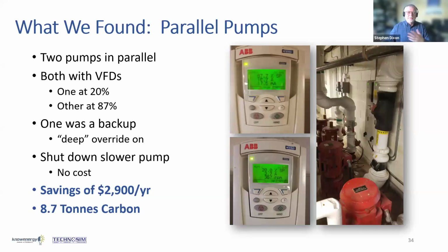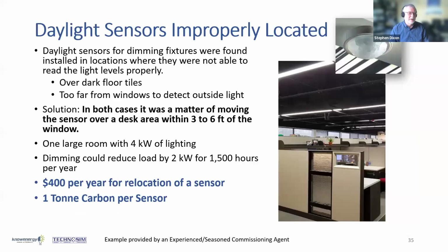As a result of some work, we did a treasure hunt in this building. I'll explain what a treasure hunt is later. It saved $3,000 a year and 9 tons of carbon just by turning off something that didn't need to be on, and equalizing the wear and tear in the pumps, because it turned out one pump was running all the time at higher flow than another. So this was a way to actually improve the reliability of the system as well.